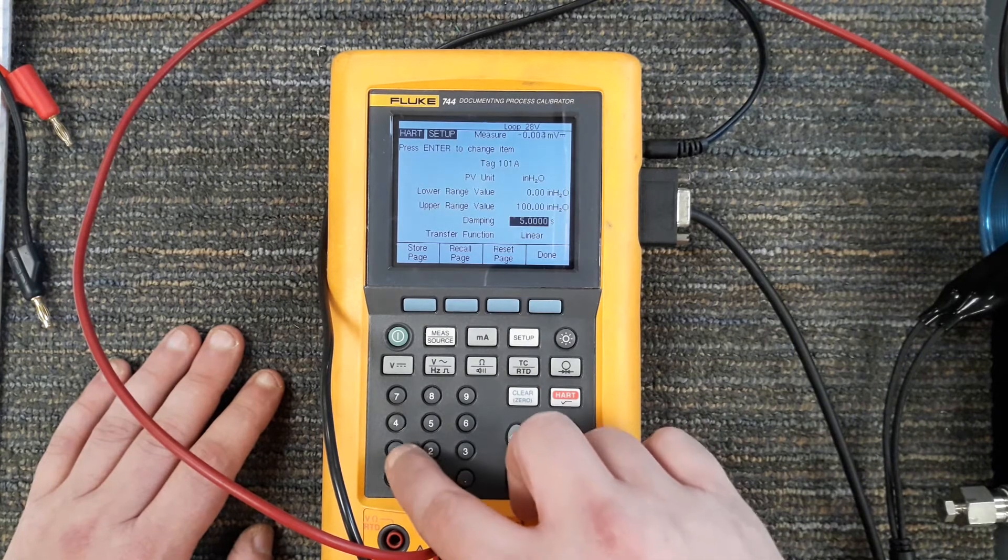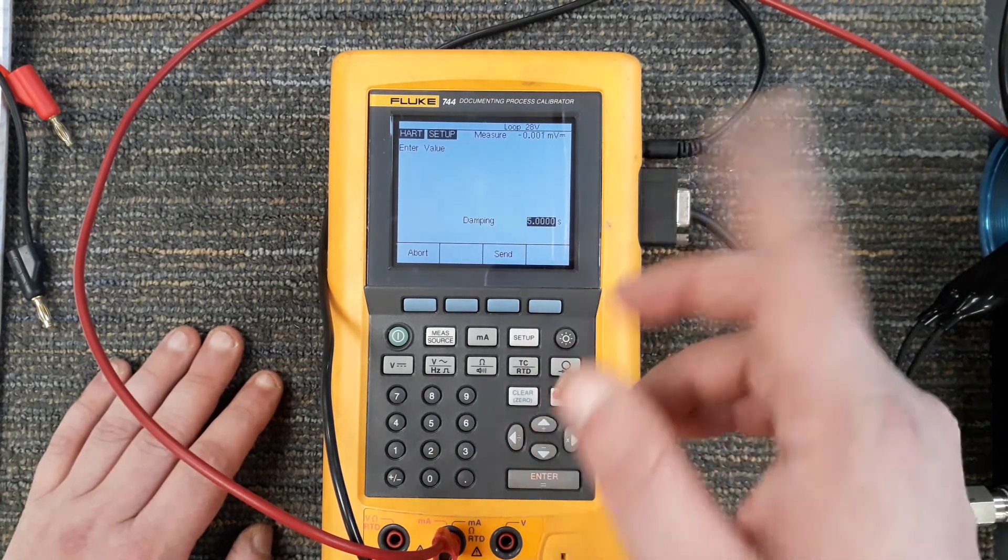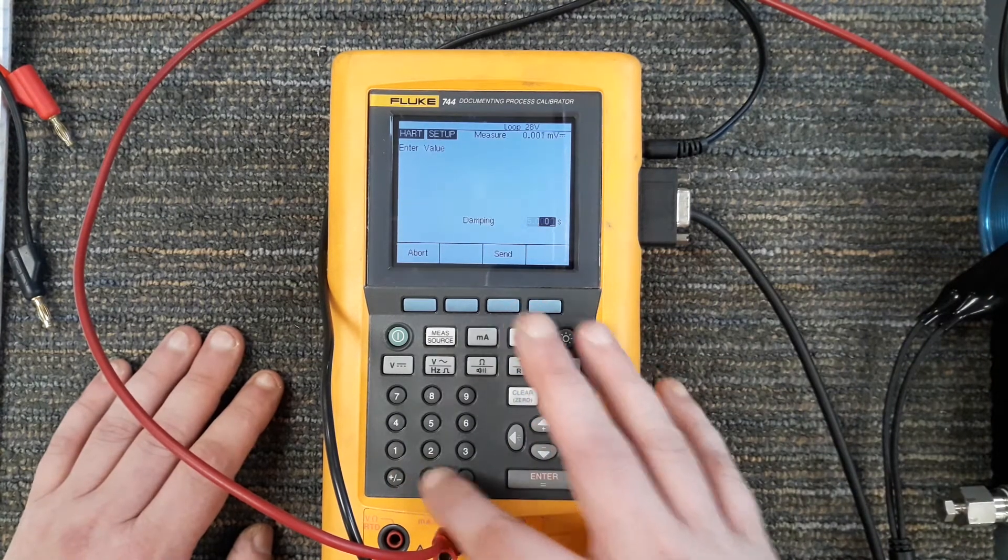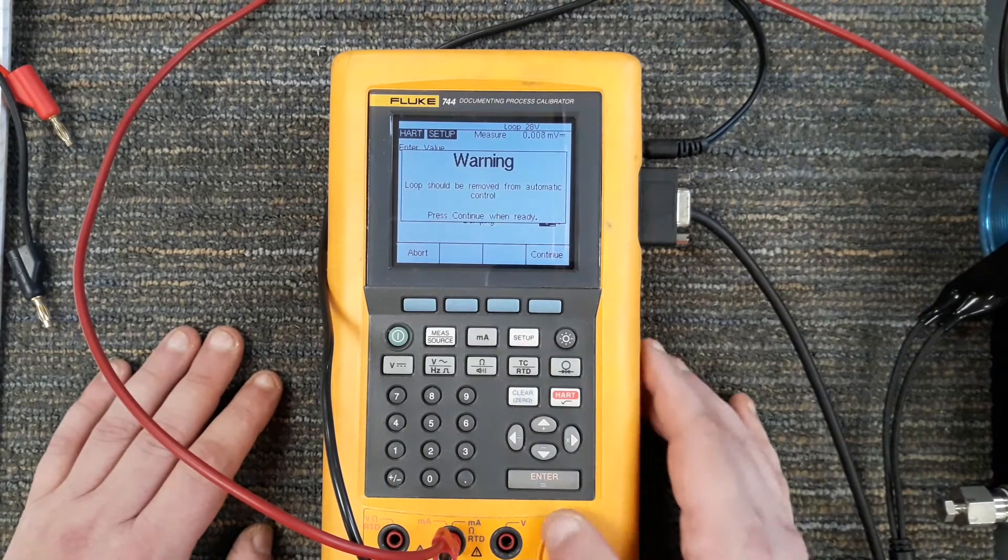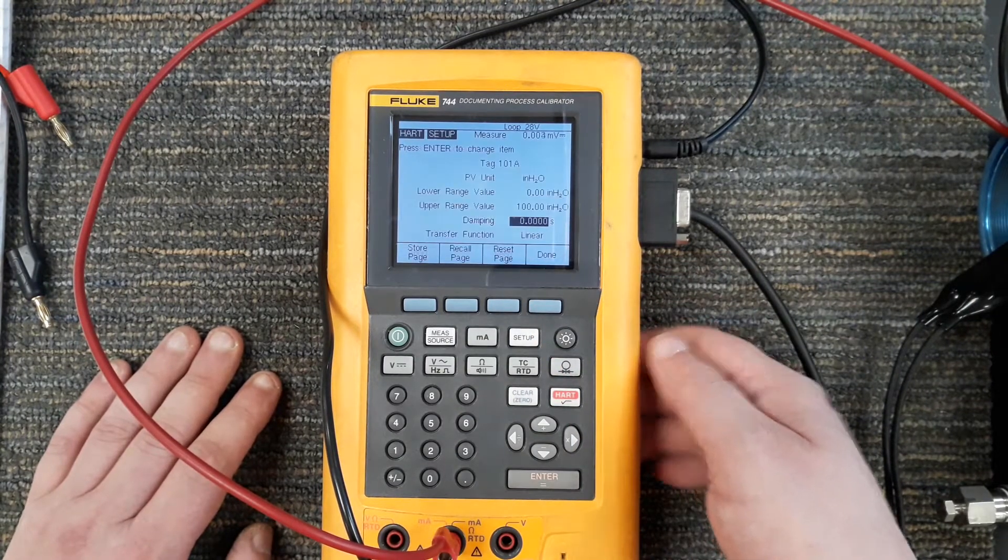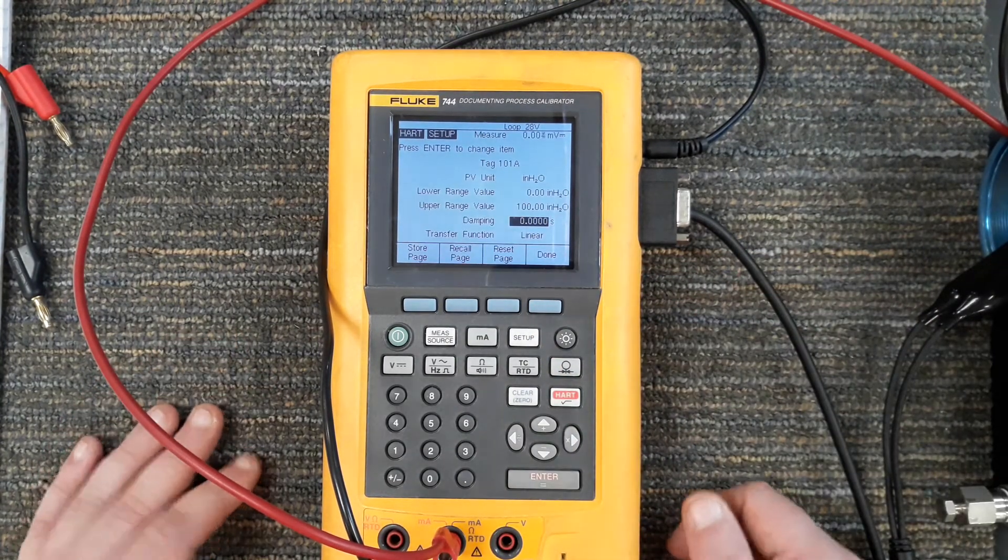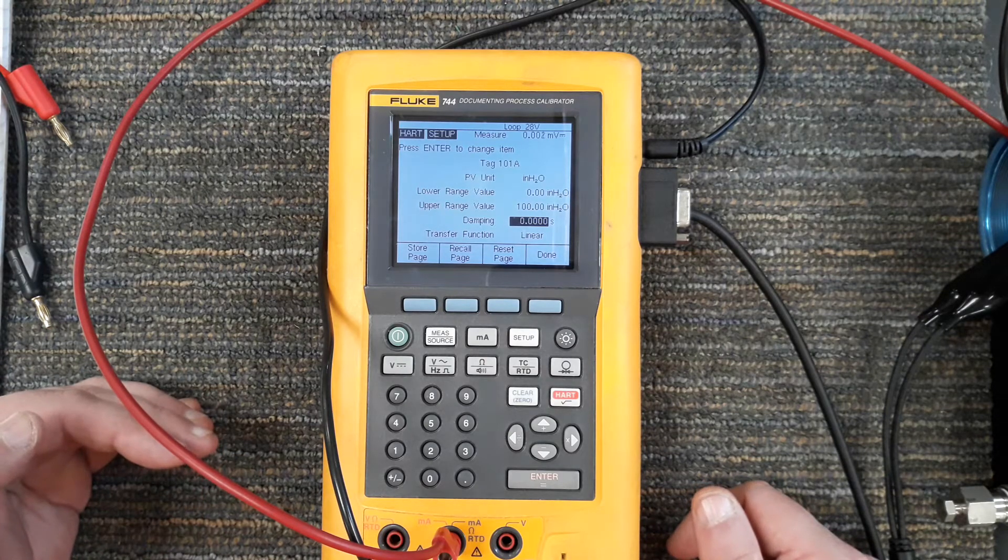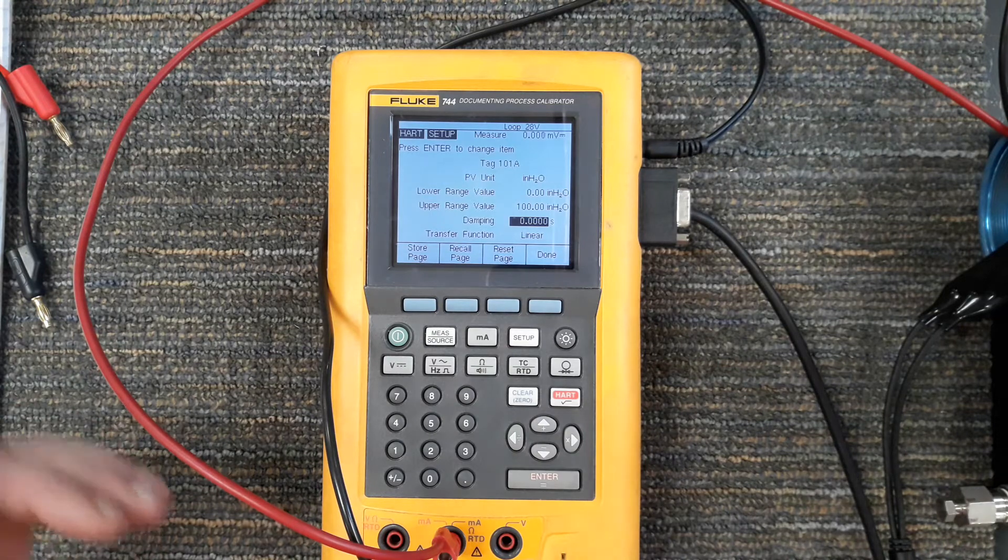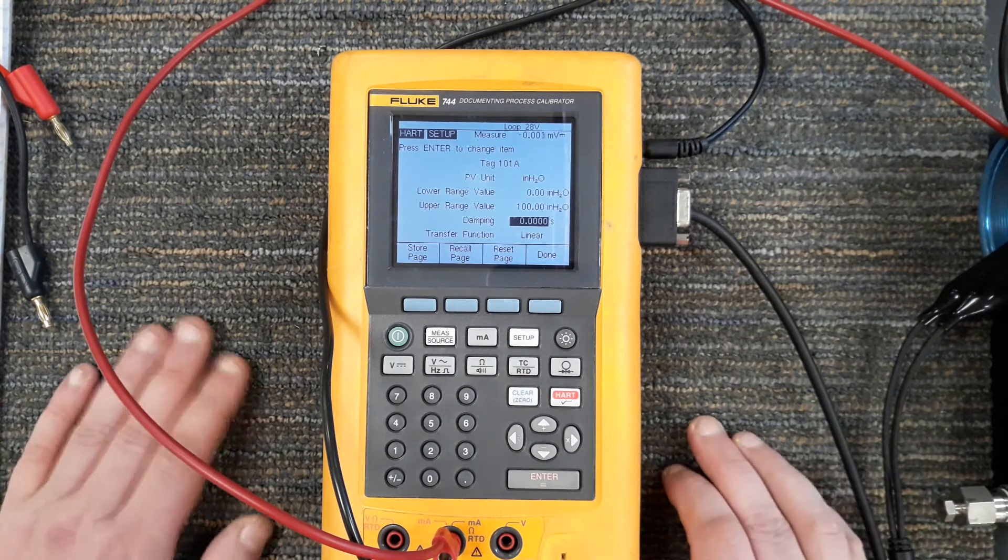A damping of five is actually going to take 25 seconds, which is huge. Normally we want a low damping. There are max and mins based on the transmitter. I'm going to try to go to zero. I'll put zero seconds so in the exact moment a change happens on the sensor, the output is going to change at the exact same ratio, almost instantaneously.